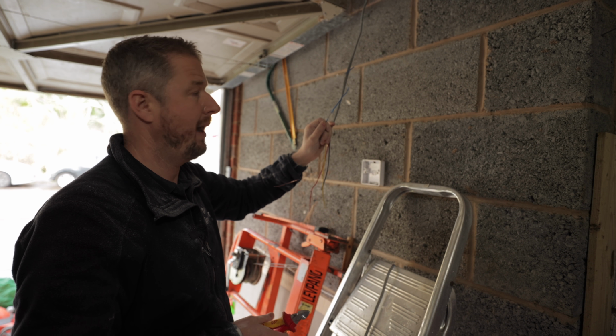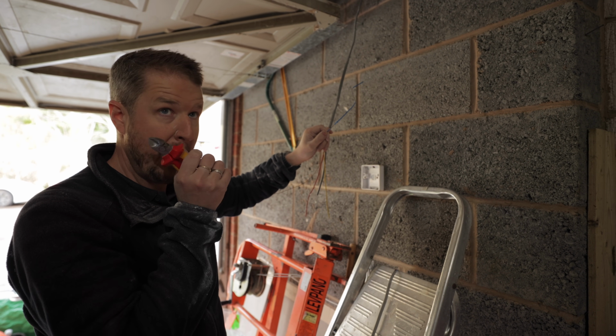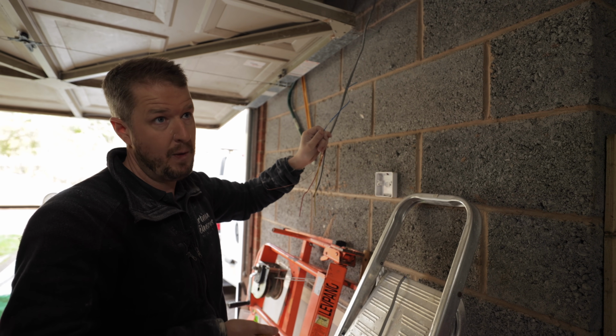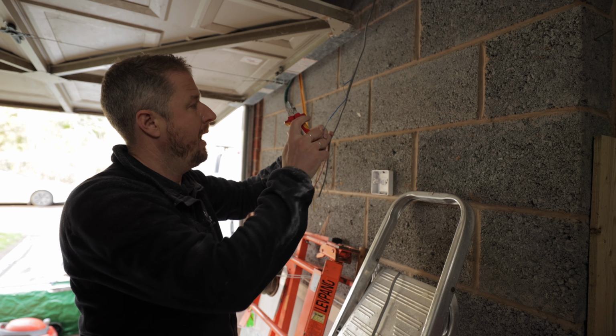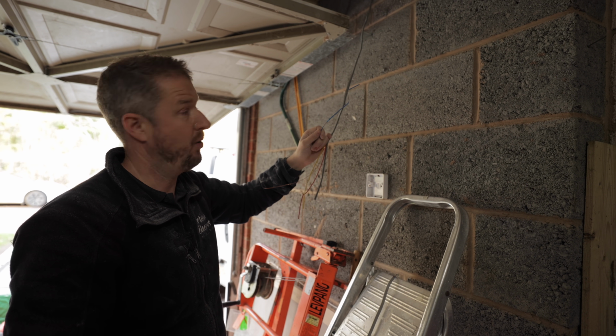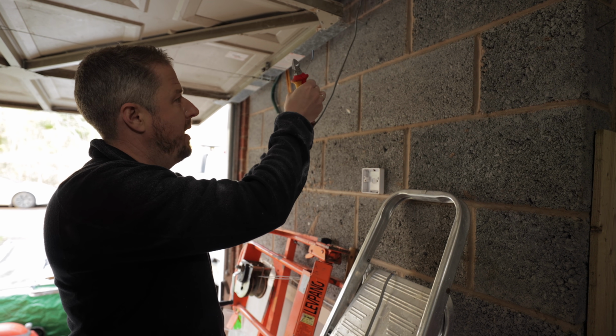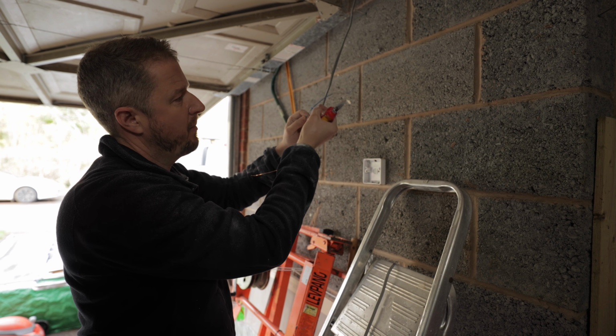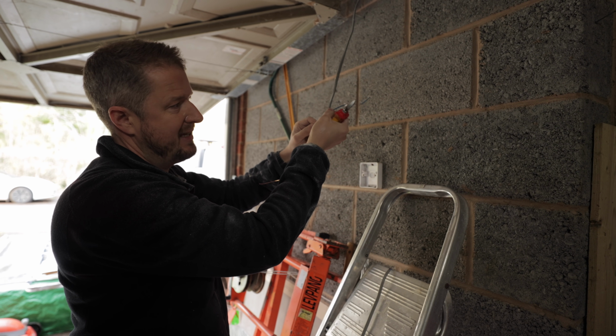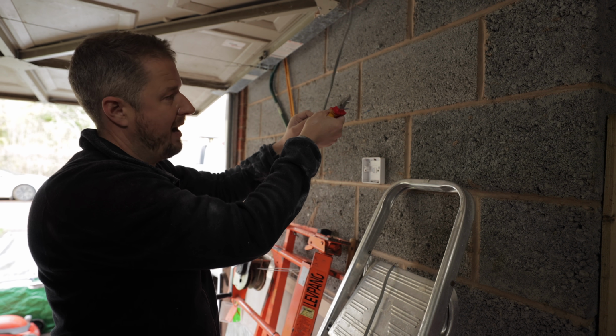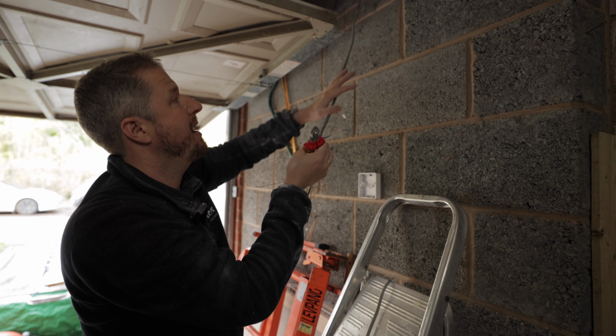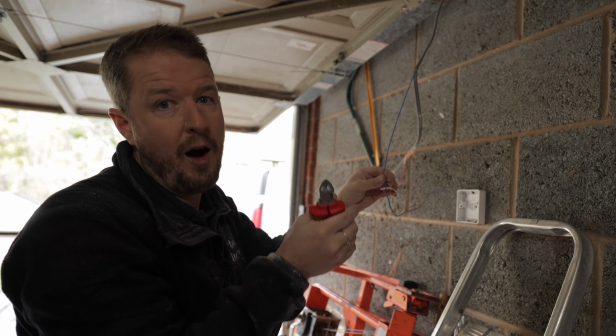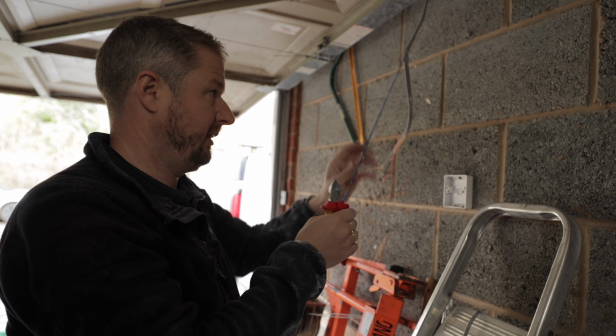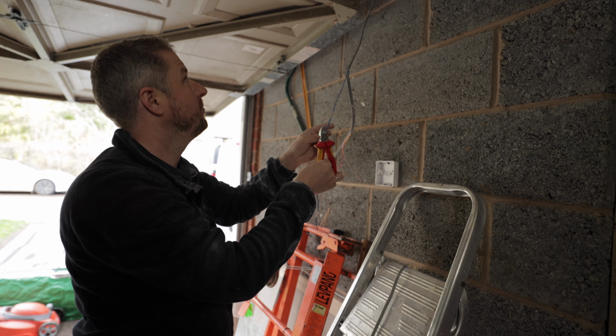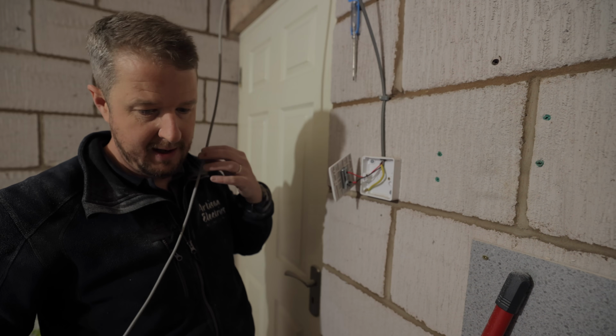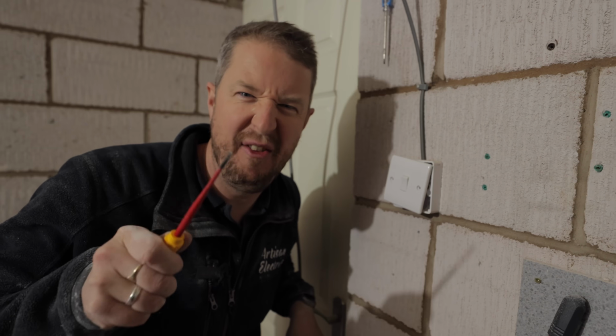Buy cheap cables, and often in these houses, this has been like this since it was built, right? But basically they probably were buying cheap cable to build all of these new houses, and they've had one faulty drum of 3-core, and the entire length of this wire has corroded, which says to me that there's some kind of conductivity in the insulation of this cable, which there shouldn't be. And that has caused this issue. And basically the whole sheath of this cable has become live, just enough to leak that voltage to the entire building. All the way along, the wire is black. I think that's the most unusual fault I have ever experienced. That nearly beat me, but we never give up.